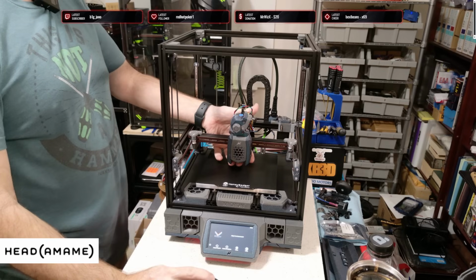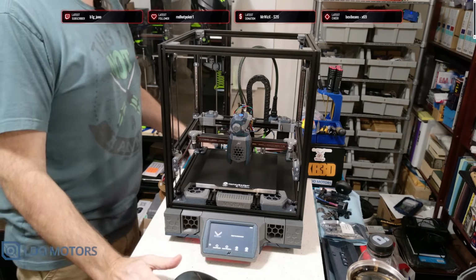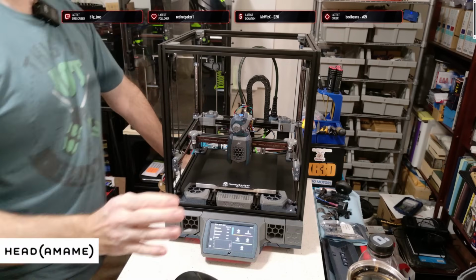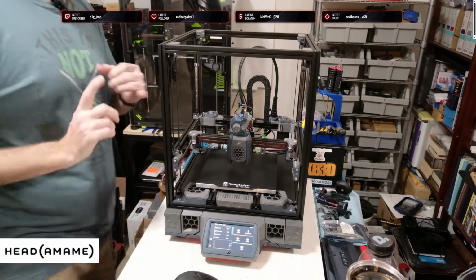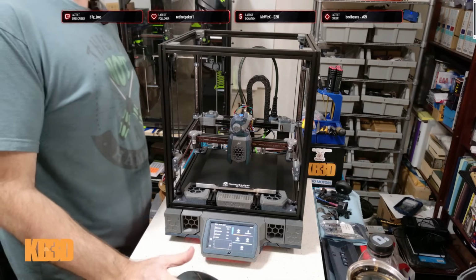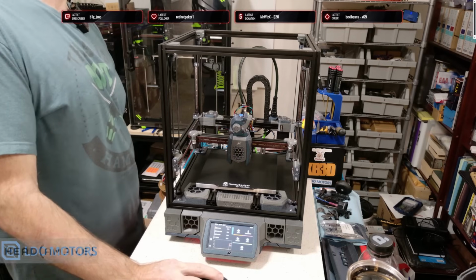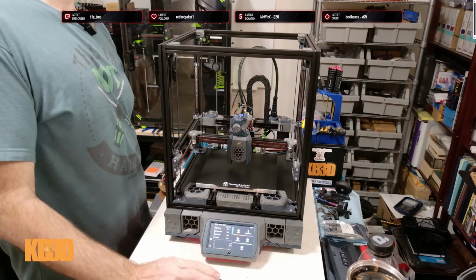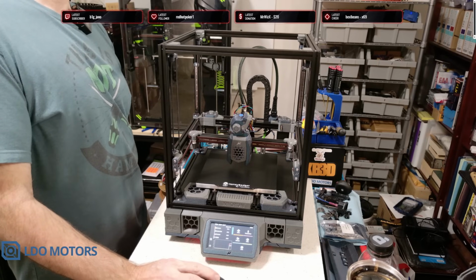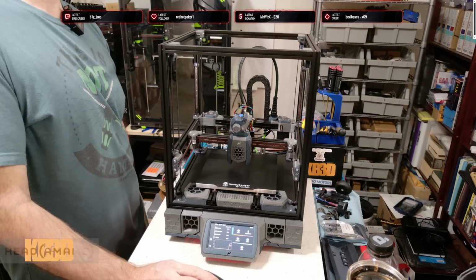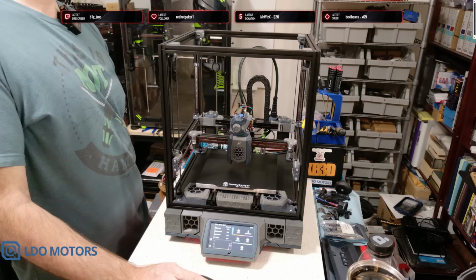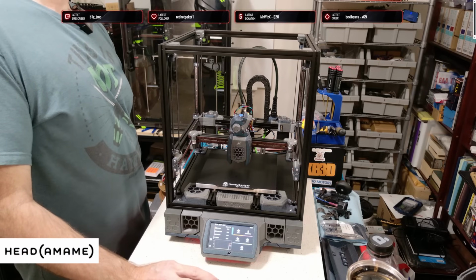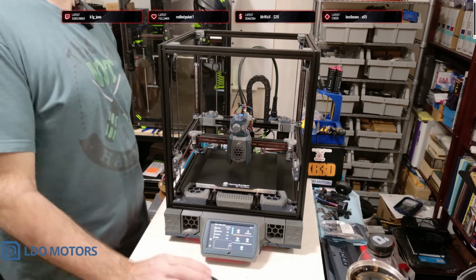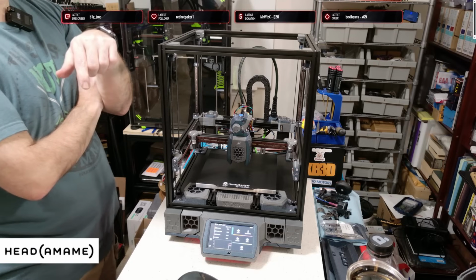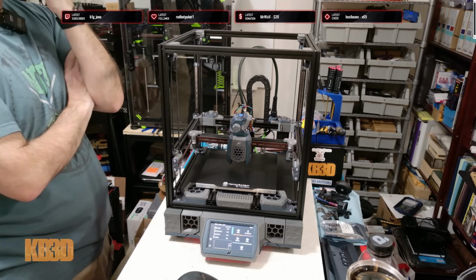So that seemed a little too much. So where are we at? We're at 4, so we're filtered. We're on 4, right? Yes. So we're filtered and we're on the lowest threshold setting, I think. We're on 4. 4 is threshold of 5. Trigger detect, filter is active. Safety trigger is active. 10 and 15. So the higher the threshold, smaller numbers is more sensitive. So the smaller number should be best and give it the most sensitivity.